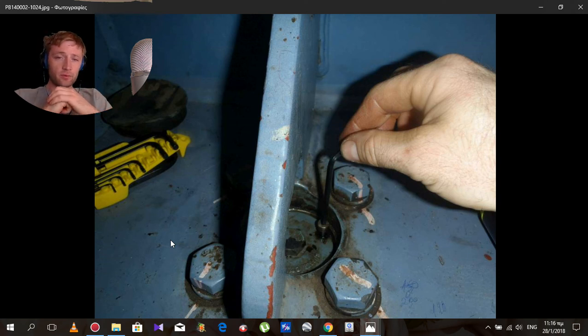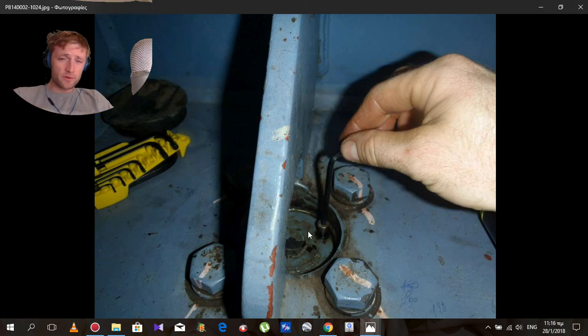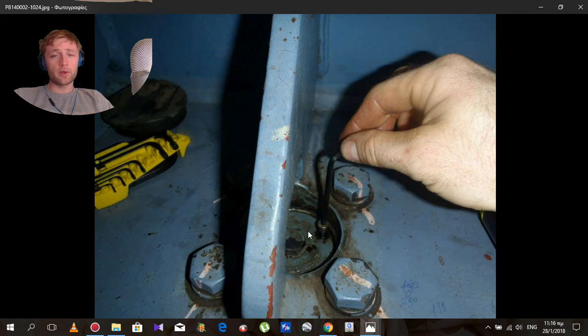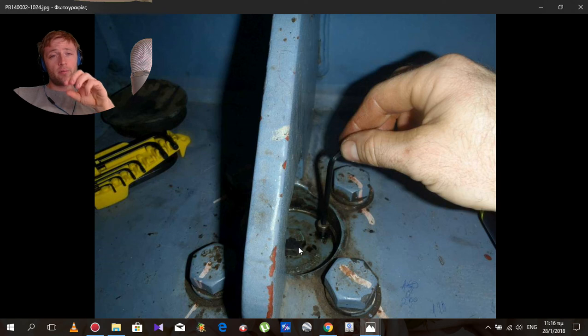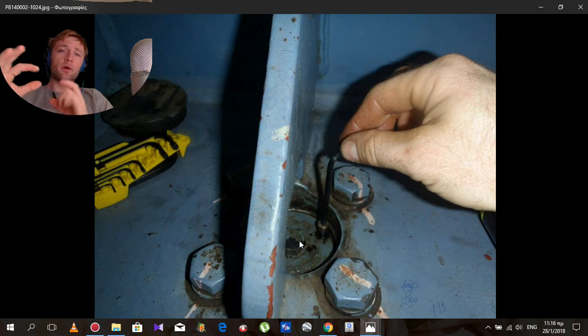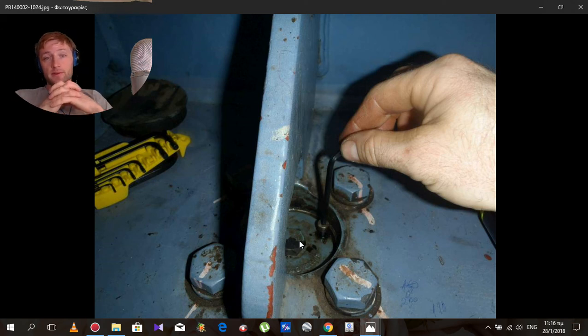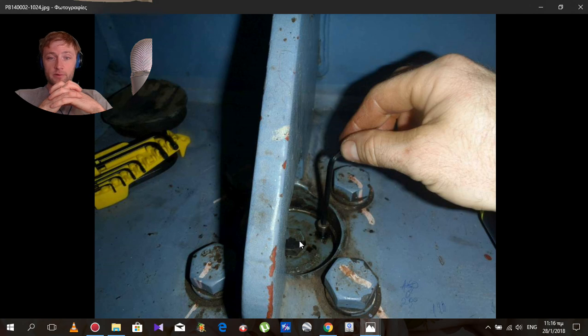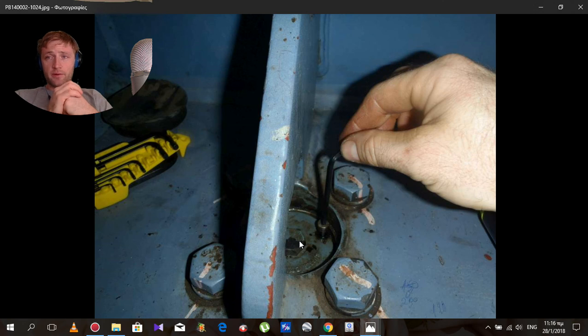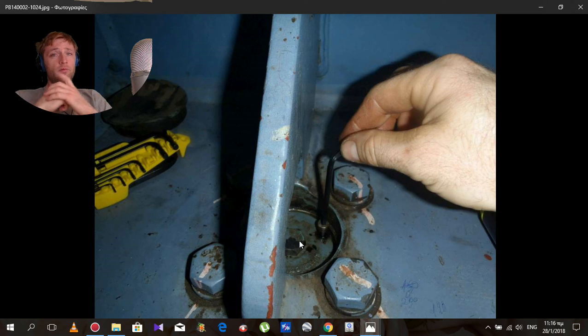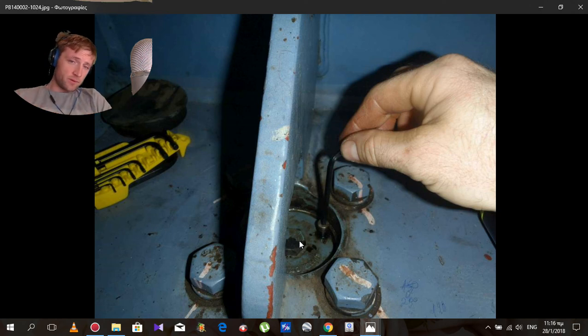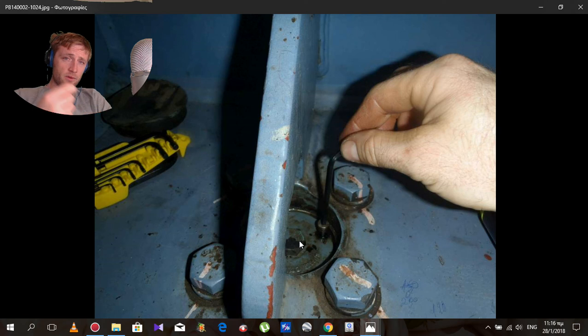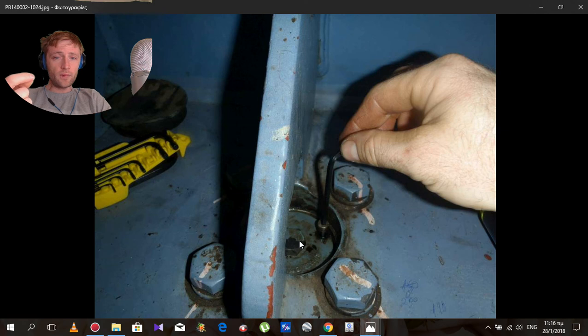So be careful to clean the threads. Do not overtighten these bolts because these bolts are only for locking this cap and preventing your inner bolt from moving. It's only a lock cap. Do not overtighten, as I said again, because next engineers will have trouble releasing that. This is the most common problem we face on board: overtightness. It's a bad thing. Just imagine how small this bolt is and how small pressure this bolt needs.